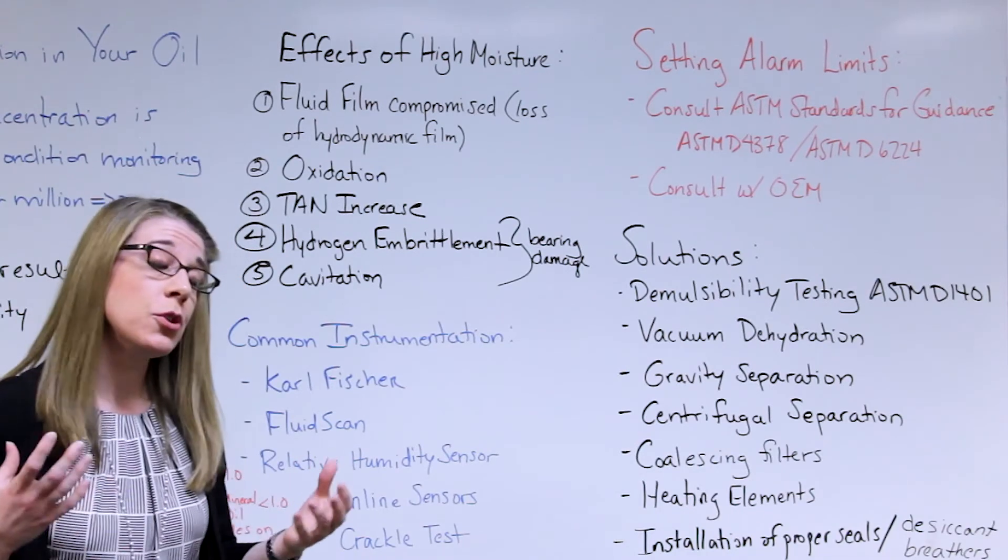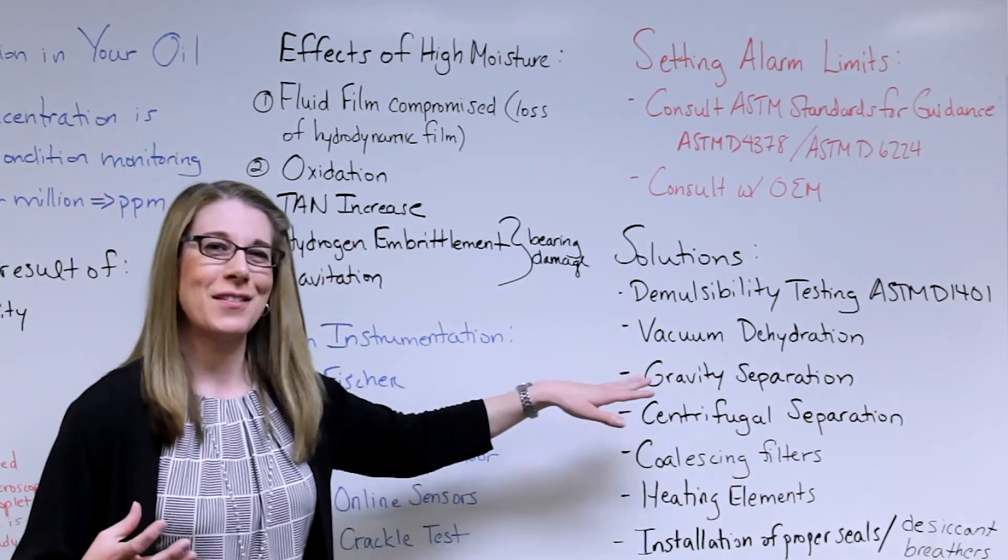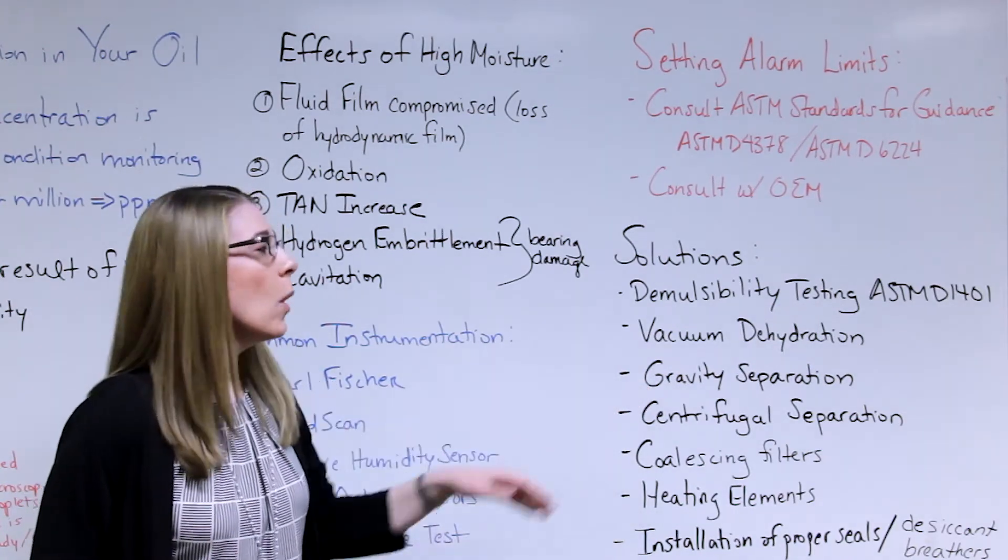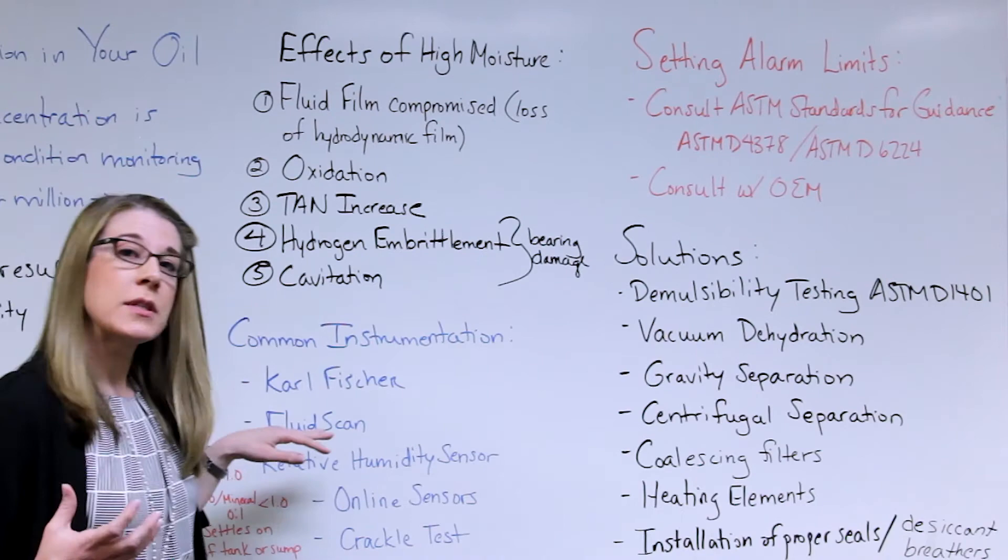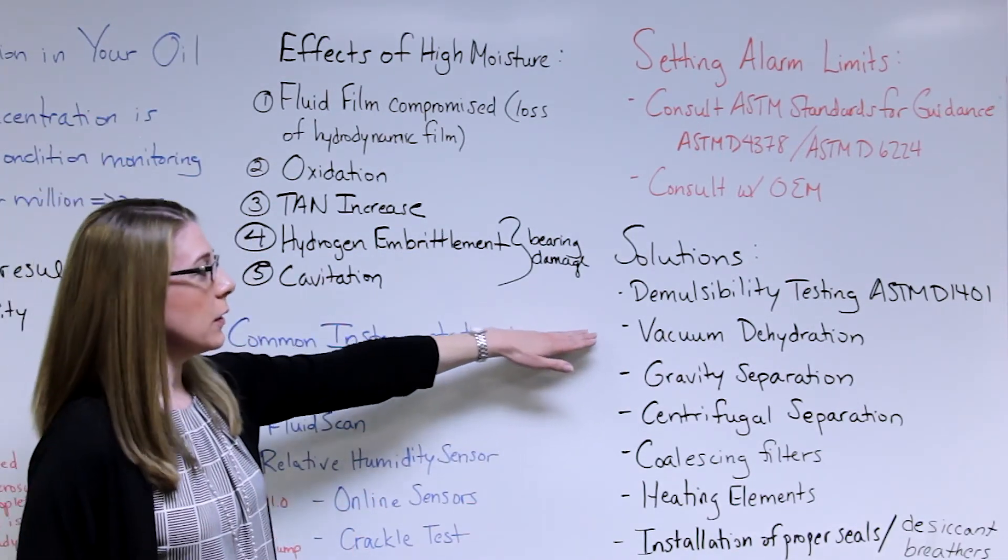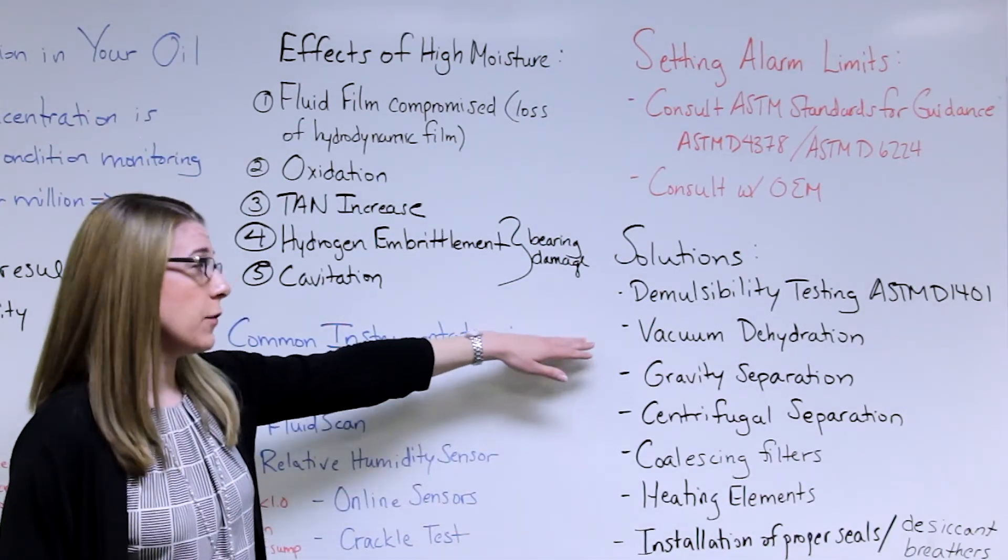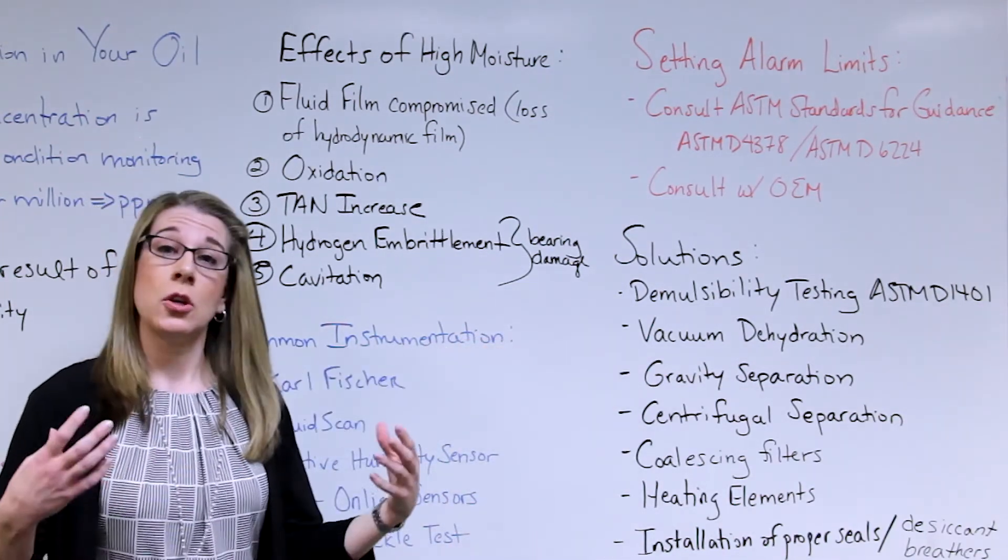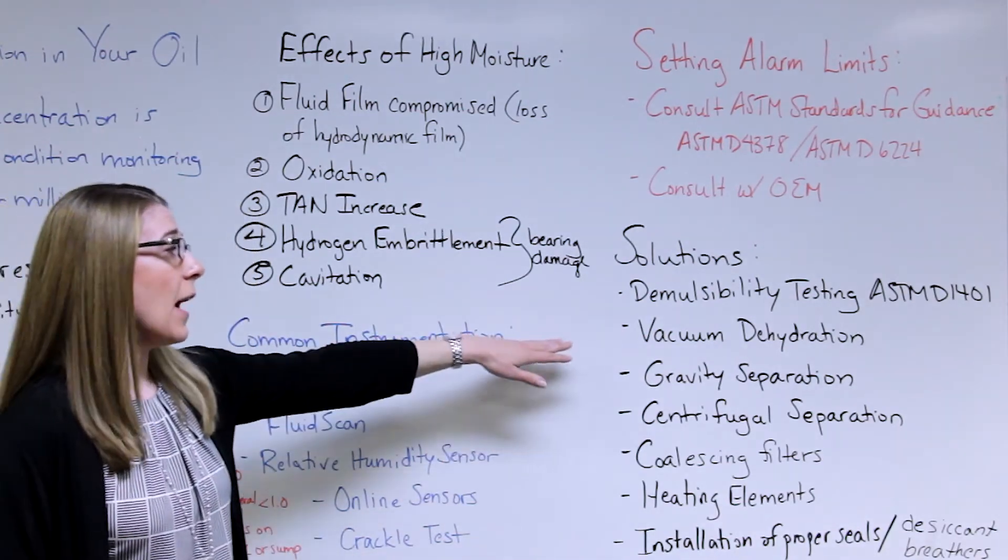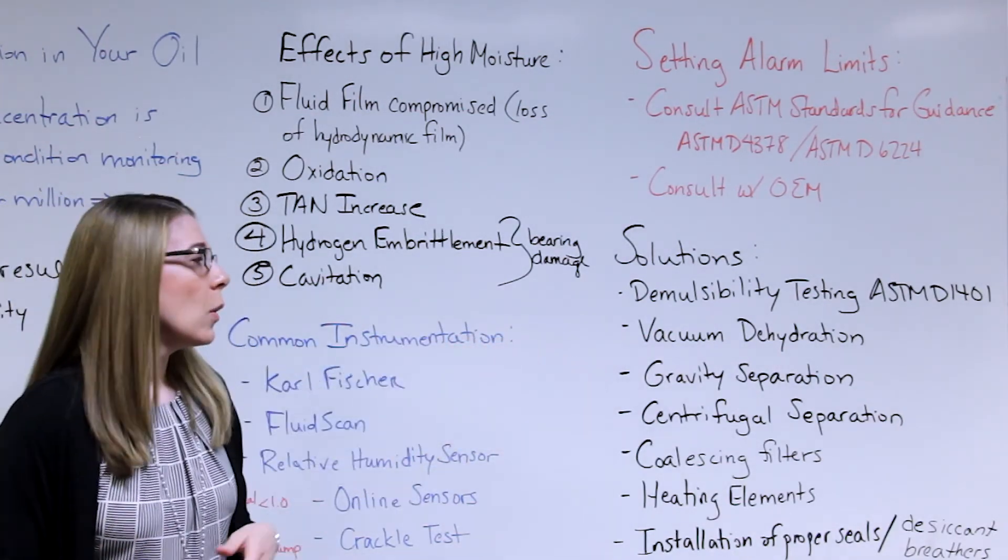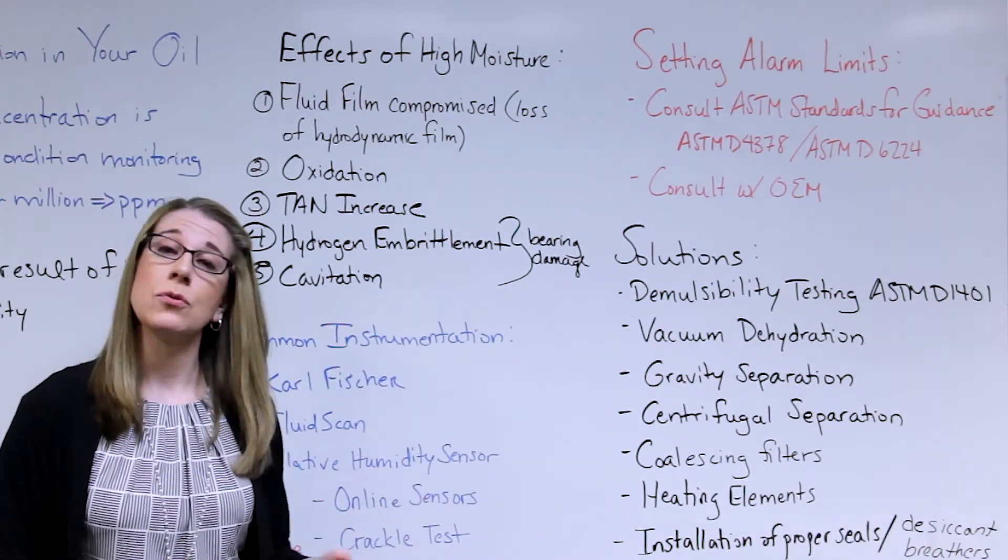When you're doing these techniques, once you choose a technique, it's important to understand what the effectiveness of the technique is. Utilizing the FluidScan would be a great on-site tool to monitor how these methods are being effective. If you're using a vacuum dehydration method, you could literally take a sample every hour to make sure that the water concentration is coming down. It's a good way to use it on site versus having to outsource it and wait for those results.